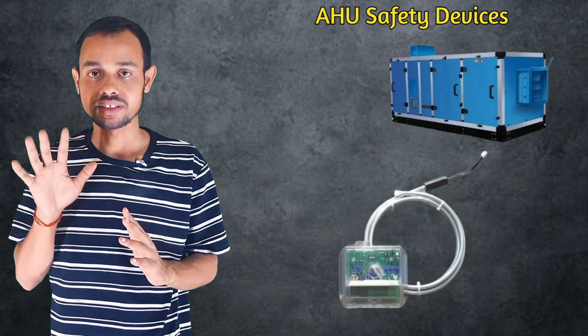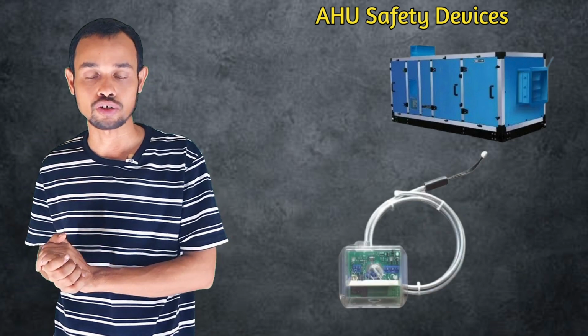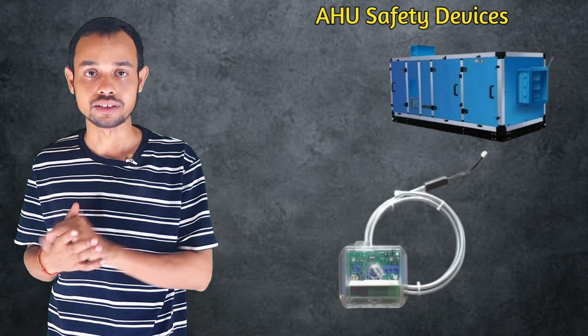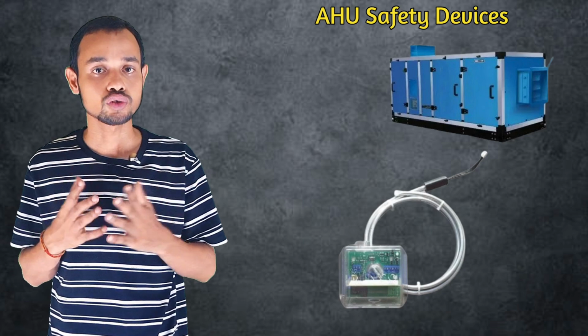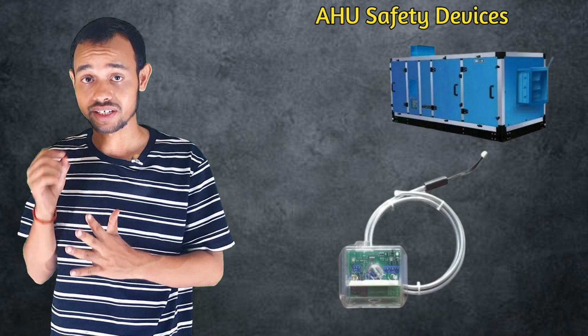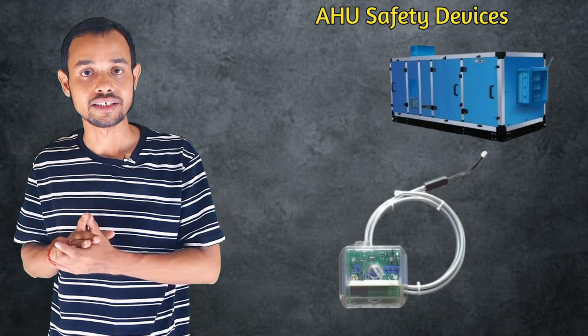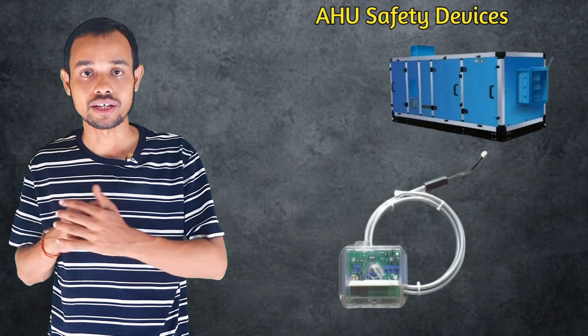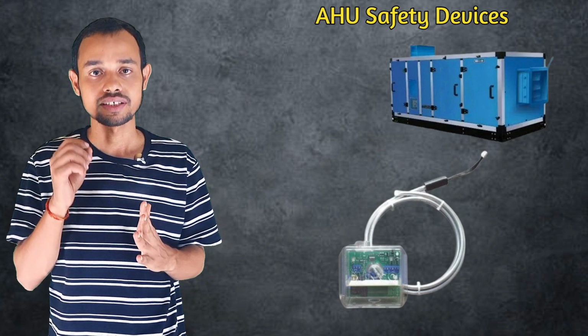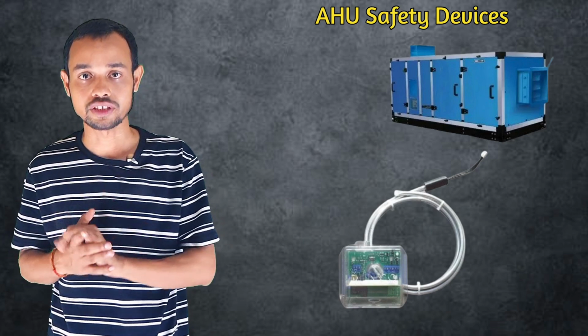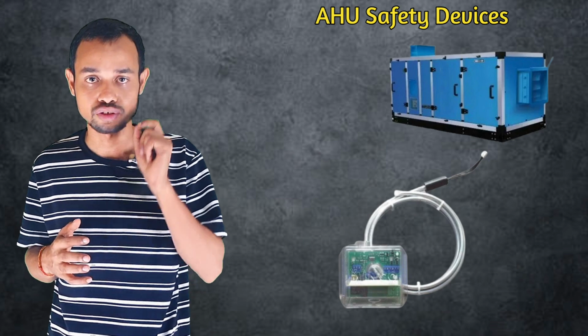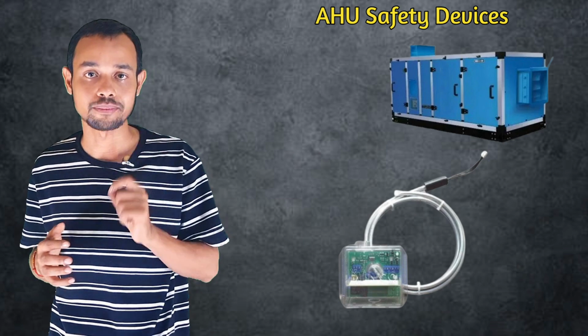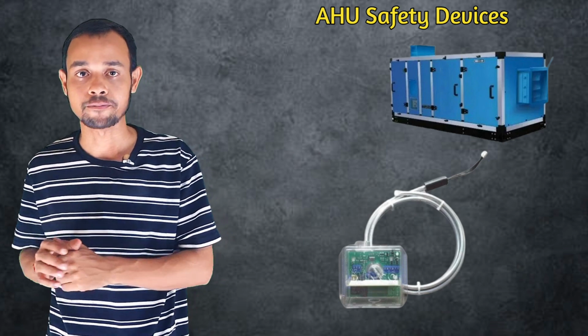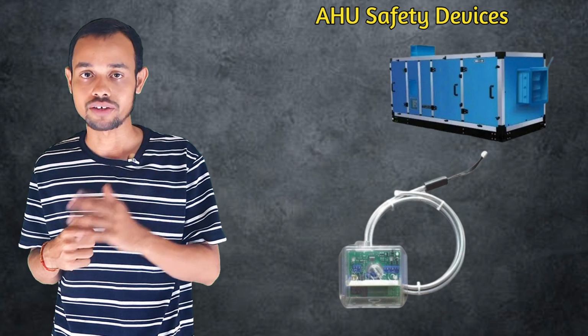And fifth is the freezestat, a low temperature cutoff. Let's see the feature of this. In a cold climate, the AHU coil may freeze, which can lead to water leakage and coil damage. The freezestat monitors the temperature and switches off the AHU as soon as it goes below the limit. Let's see the usage of this: system protection from coil freezing.